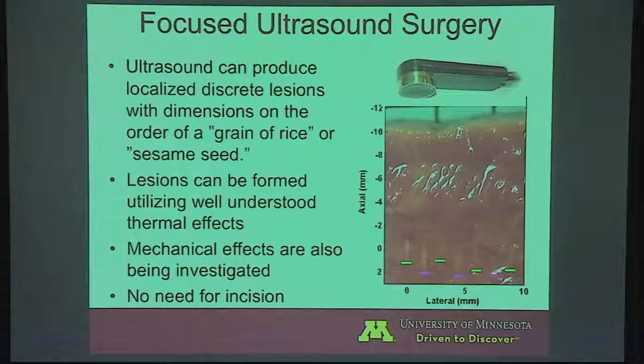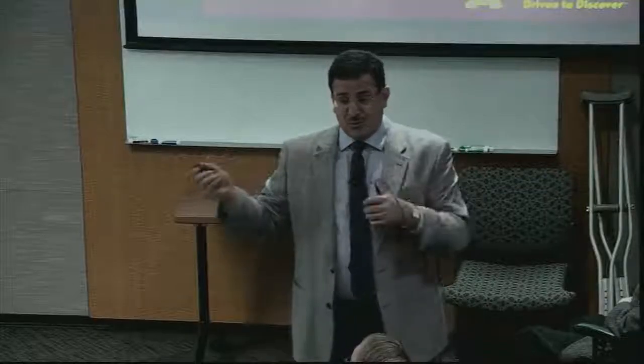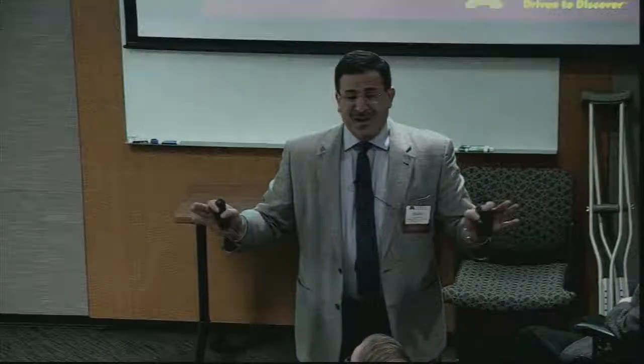As somebody pointed out, what are these bars? This is where you can predict where the lesion starts. And then it actually grows towards the transducer. Our contribution to this field is we have introduced this dual mode array concept that allows us to track and actually control exactly the size of this in real time with millisecond or sub-millisecond resolution. That's our unique contribution to this area. There is a lot of electrical engineering behind this, but it's applied for a good cause, I hope.